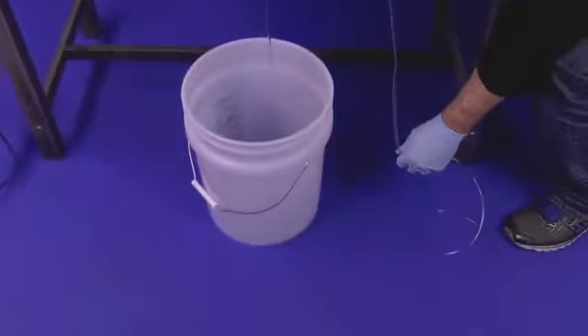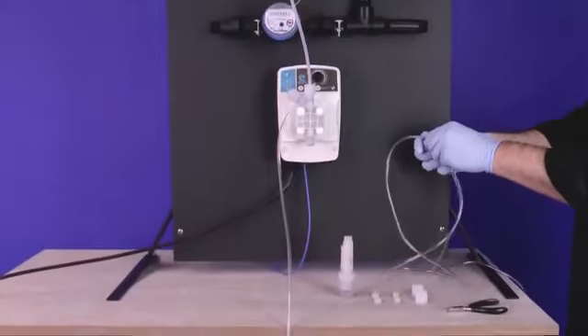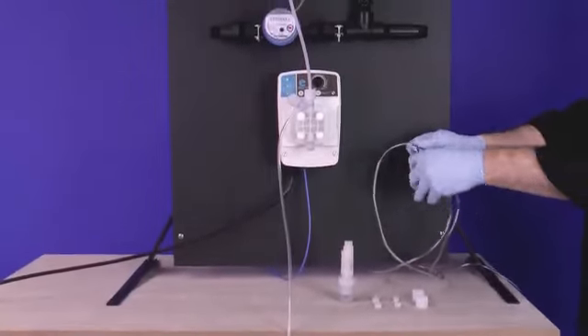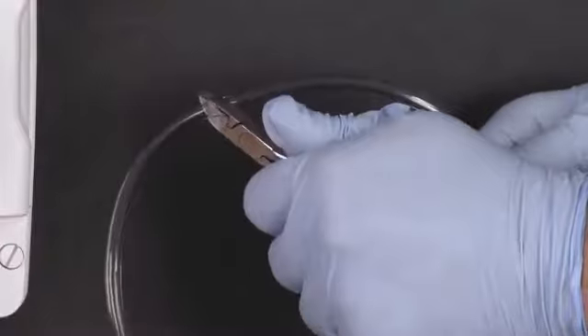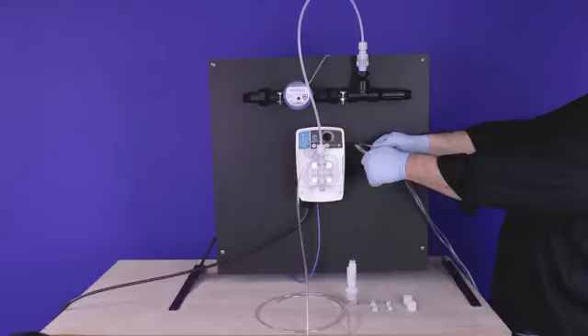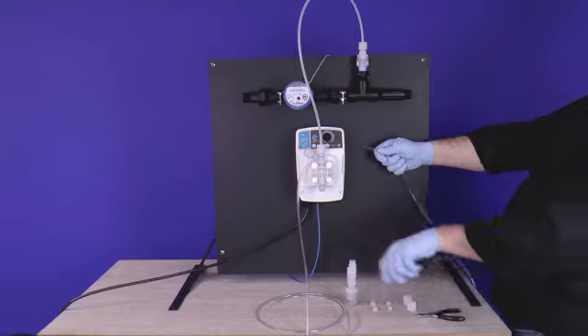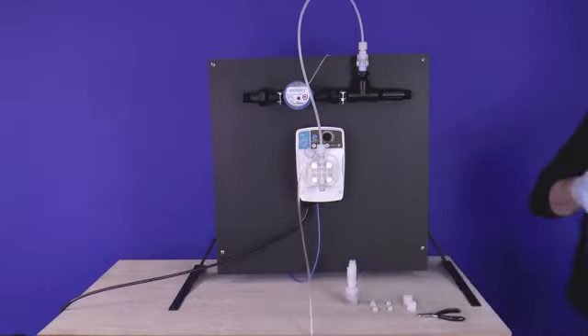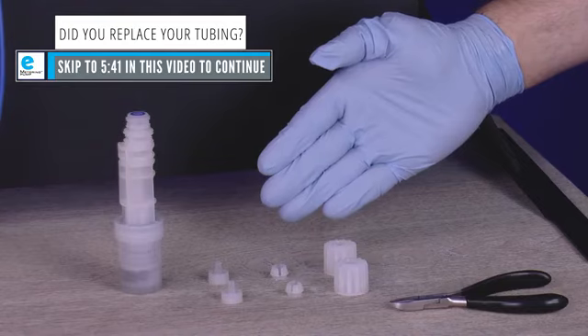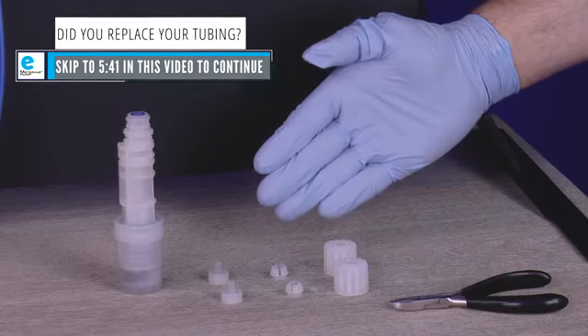Estimate the length of tubing you will need by measuring from the suction valve to the chemical bucket. Using the diagonal pliers, cut the PVC suction tubing so that the foot filter will comfortably sit around 2 inches from the bottom of the chemical bucket. Set the remaining PVC tubing aside. If you just replaced your tubing, skip ahead in the video to prep your tubing connections.